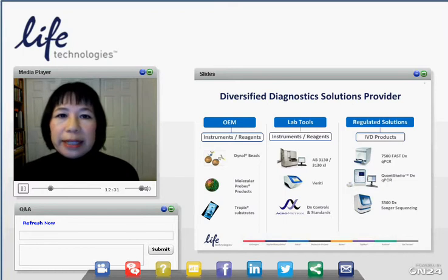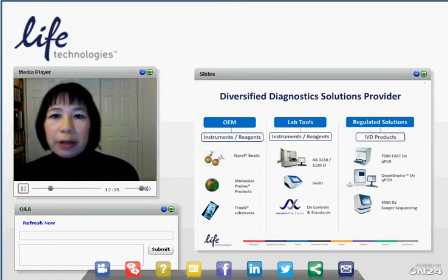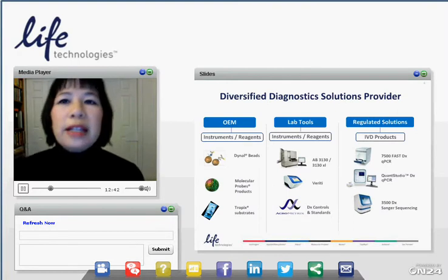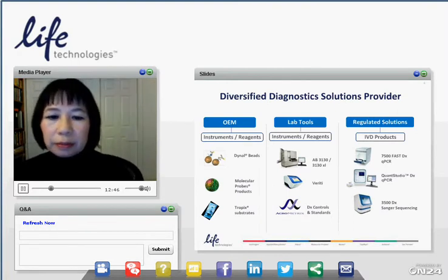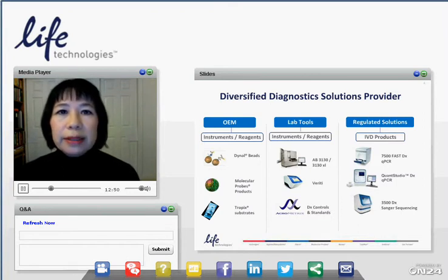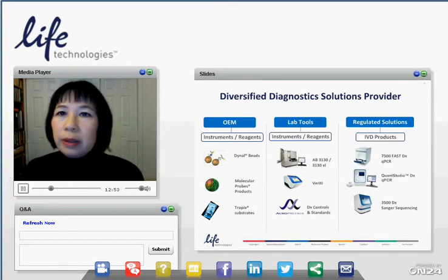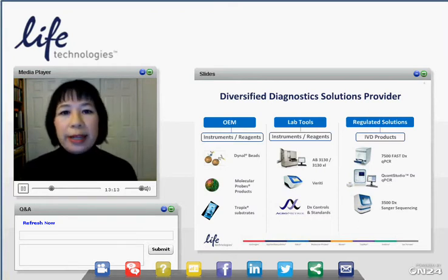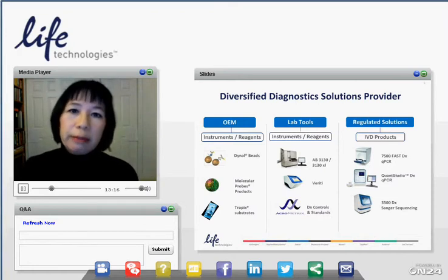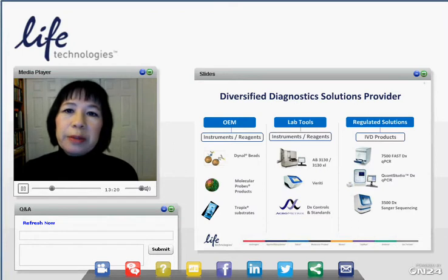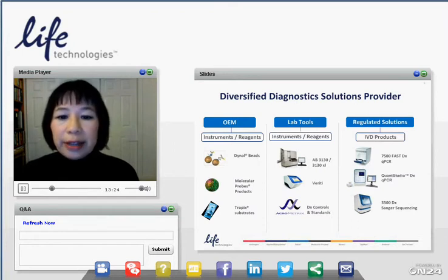Right in the middle there is the Veriti DX thermal cycler, which is the first Applied Biosystems endpoint thermal cycler for in vitro diagnostic use. The Veriti is classified as a U.S. FDA Class 1 medical device. It conforms to IVDD requirements and is CE IVD labeled in Europe. The instrument is manufactured to ISO 13485 and GMP requirements. The instrument is available in 3 formats for thermal cycling: 96 well, both standard and fast, and standard 384 well. All 3 systems feature an exceptionally easy-to-operate color touchscreen to simplify instrument setup and use. This instrument is available in the U.S., Europe, and other selected countries.